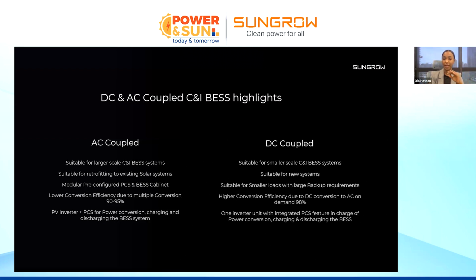Therefore, the overall efficiency can go between 90 to 95% compared to the DC coupled. And then there is a PV inverter as a model or as a unit, and there is a PCS for the power conversion, for charging and discharging the BESS systems. However, the DC coupled, of course, is suitable for smaller applications, all right? And it's suitable for new systems because this is a whole new inverter unit that you are installing. It's a hybrid inverter. It does the on-grid and the off-grid applications in one model. So it's more suitable for newer systems and smaller C&I segments.